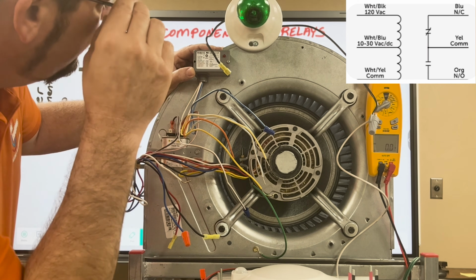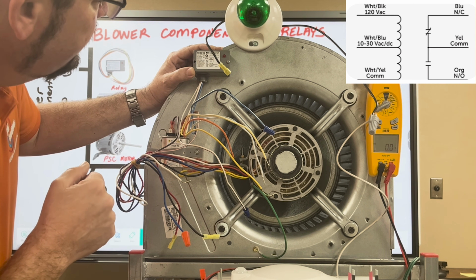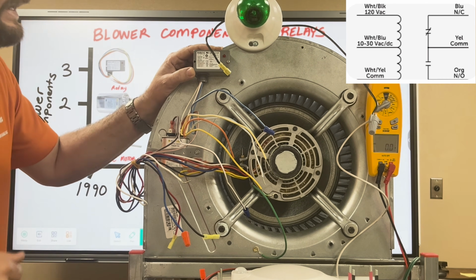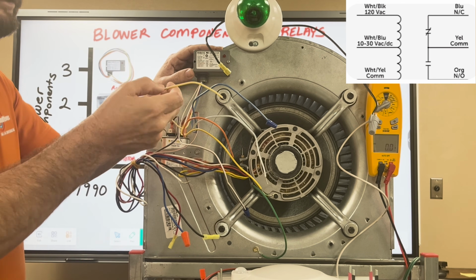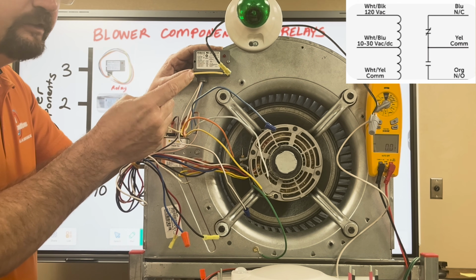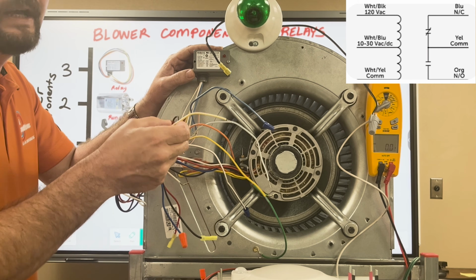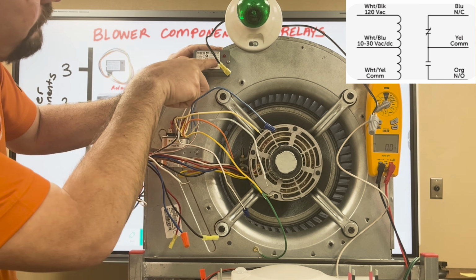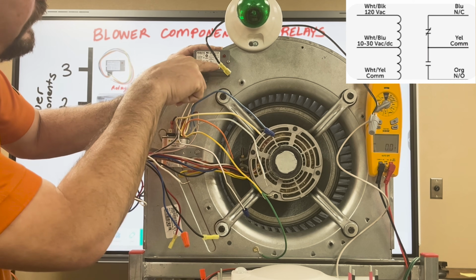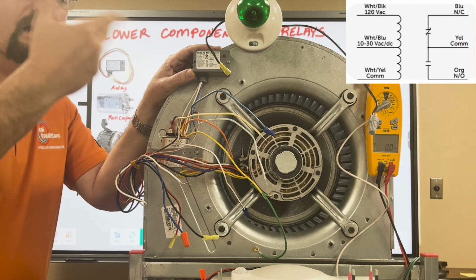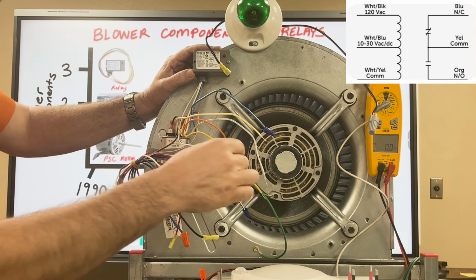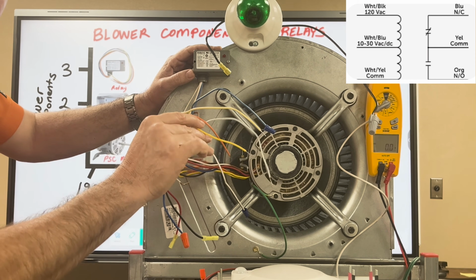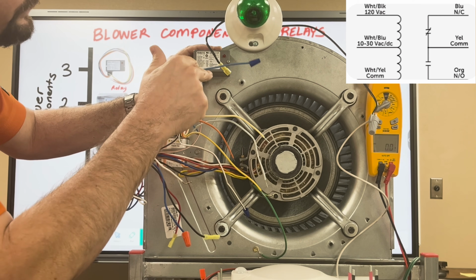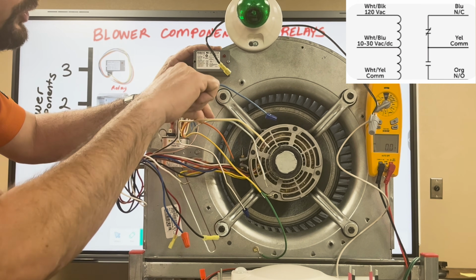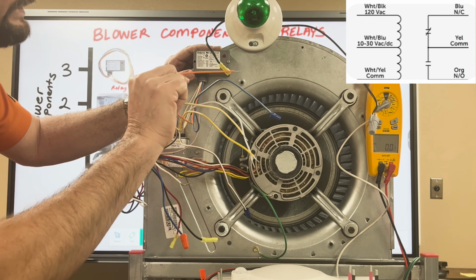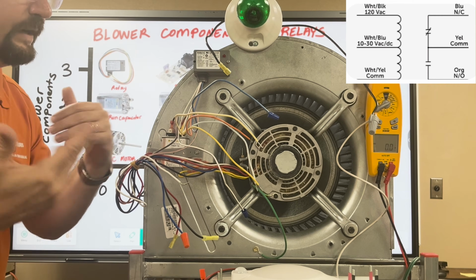We have white and yellow, we have white and blue, and we have white and black. So all the wires that have two colors on them, white with another color that's striped, that's my coil side, all right? And then I have a solid blue, a solid yellow and a solid orange. That's going to be my contact side. So one of those, the yellow, will be my common coming in, which is my input, and then my output will be blue, which is normally closed, or orange right here, which is normally open. So there are a lot of different ways we have to wire this up.